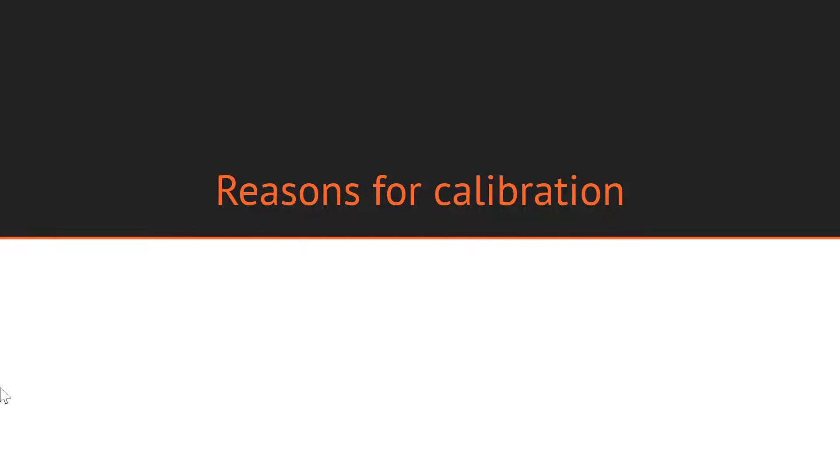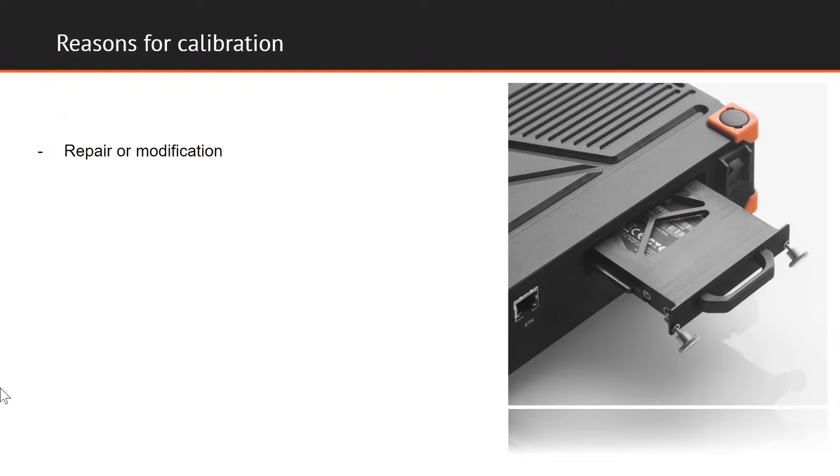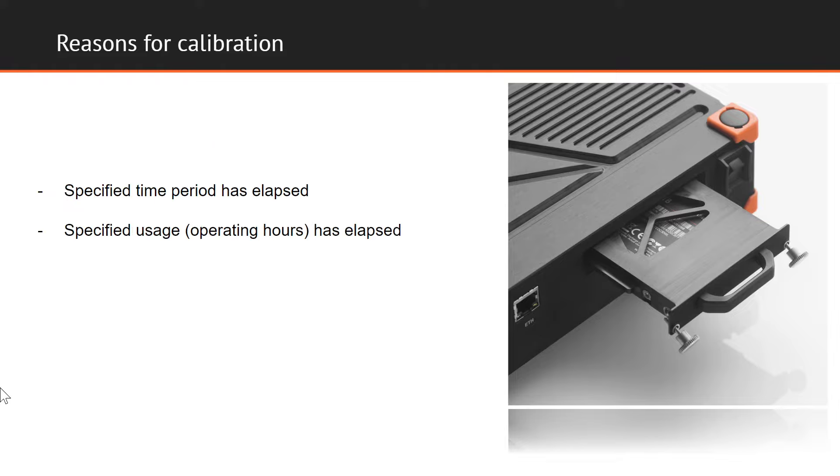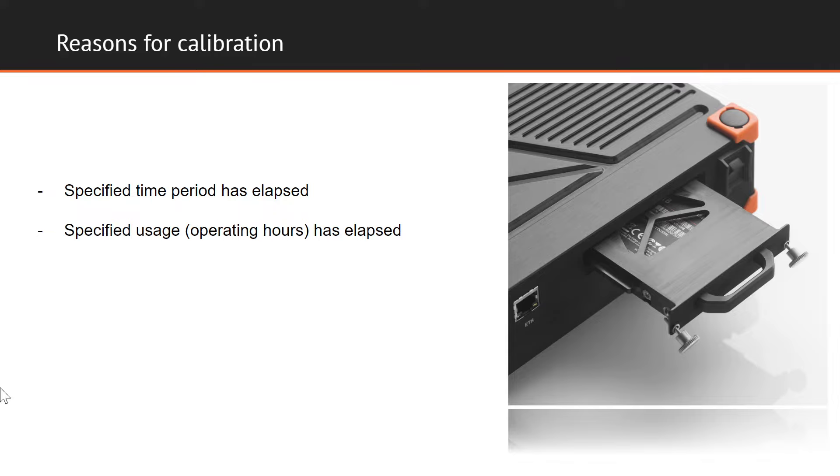Generally speaking, calibration should be performed in the following situations: whenever we acquire a new instrument that has not been utilized before, after any kind of repair or modification has been carried out on the measurement equipment, in the event of specified time period or specified usage in operating hours having elapsed, and it's also a good idea to carry out calibration before and after a critical measurement, just to ensure that characteristics of the system remain the same during the measurement process.